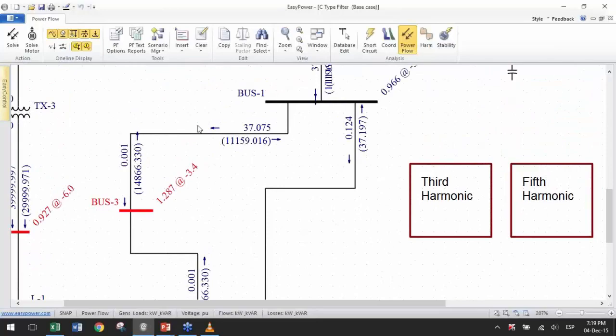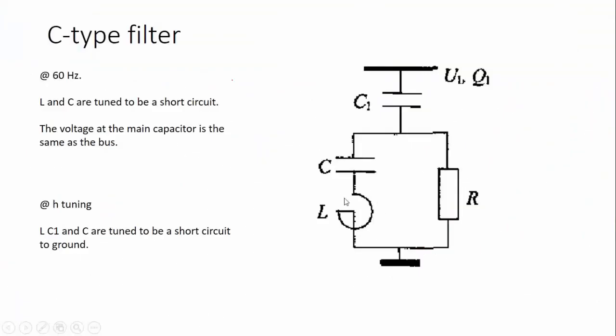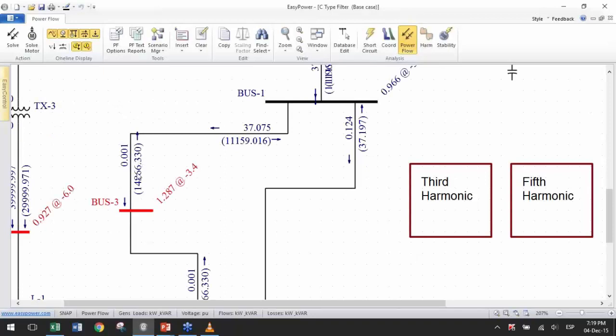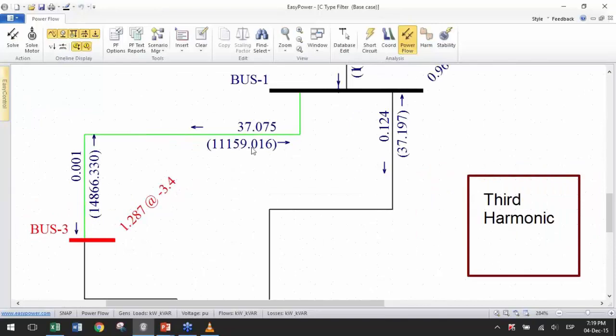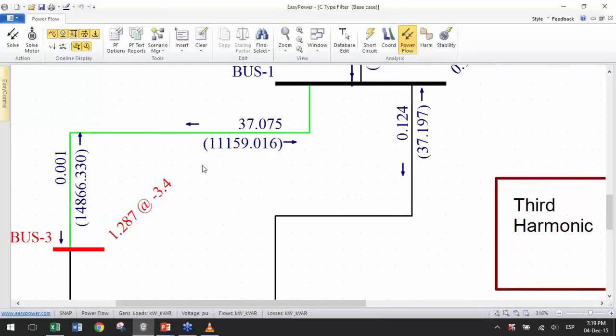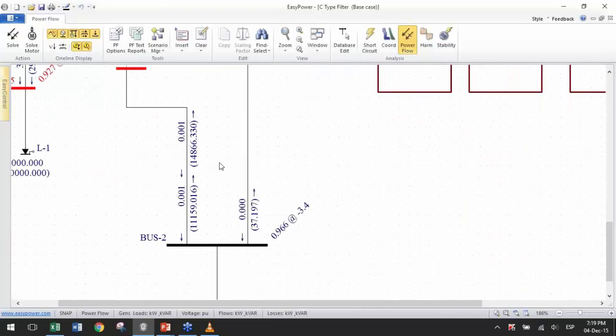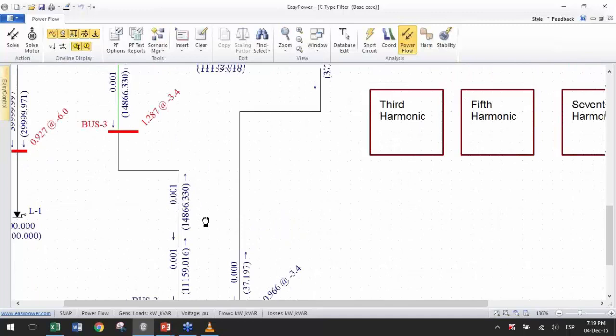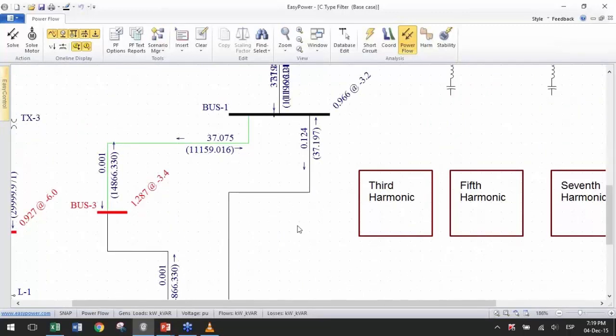But when it comes to the inductive part of the filter, which is this one, this excess power will be consumed by the inductance. Since this reactance and this reactance are the same and the current is the same, one will produce the same that the other one will consume. So in the end, what you have going into the system is 11 MVARs, which is the exact same number that got here. So whatever is going out of the capacitor goes here. And again, some of the power will flow through the resistance.